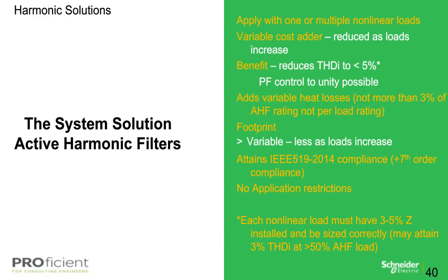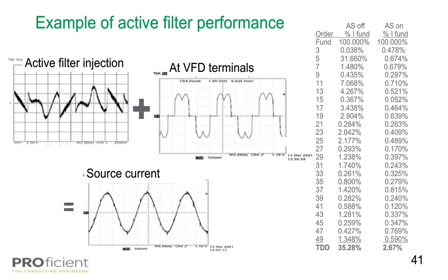So real quick, I just want to show you a sample of a test we ran, which can also be found under the resource tabs, which you'll be able to access following the presentation. This is an example of a 600 horsepower VFD with a 3% line reactor tested without and with an active harmonic filter. As you can see, the harmonic orders jump at the 5th, 7th, 11th, 13th, on down through the 41st and 43rd. The total TDD is over 35% without the filter, versus roughly 2.5% using the active harmonic filter.